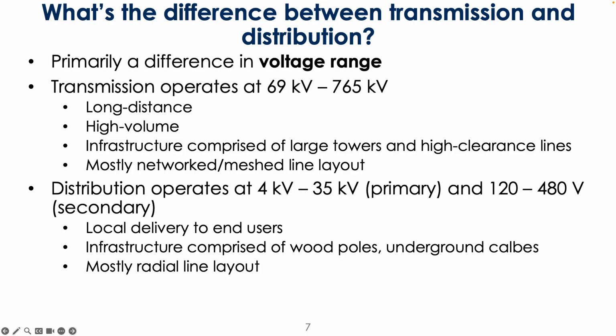Do you know what our primary distribution operates at? 12 kV. Okay. We have a little bit of 4 kV in our central cooling plant for our chillers. But the distribution is at 12 kV. We're interconnected to PG&E at 115 kV at the substation. Okay. And so 12 kV is a very typical voltage for primary systems. We're underground in central campus, and overhead in west campus and south campus. You'll hear more about it.